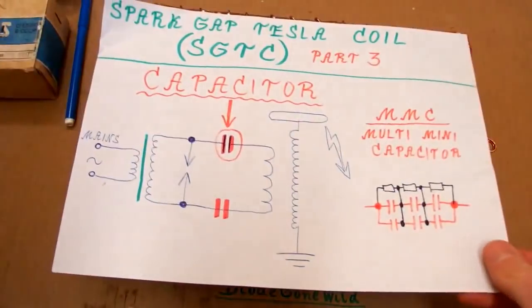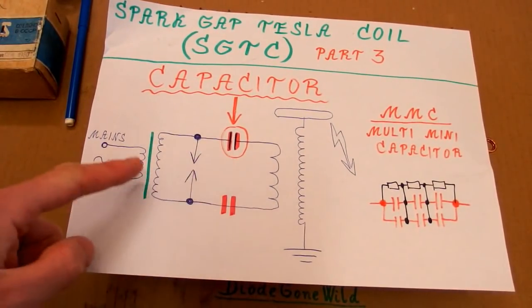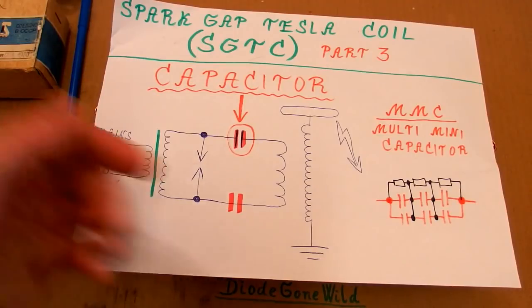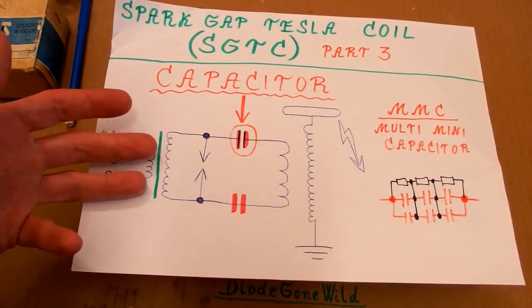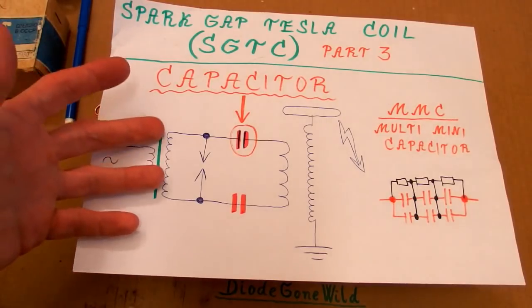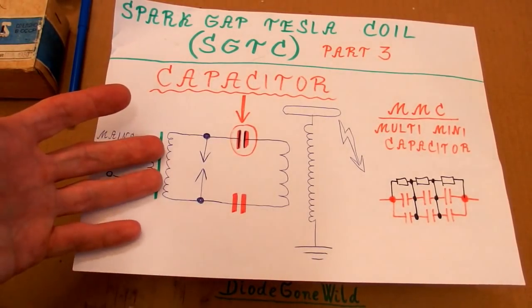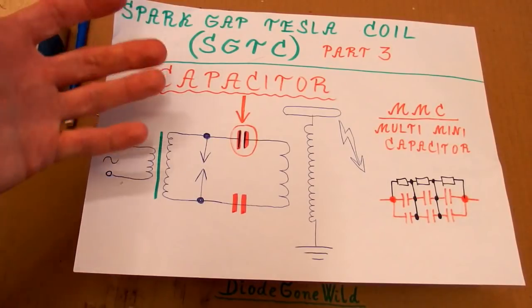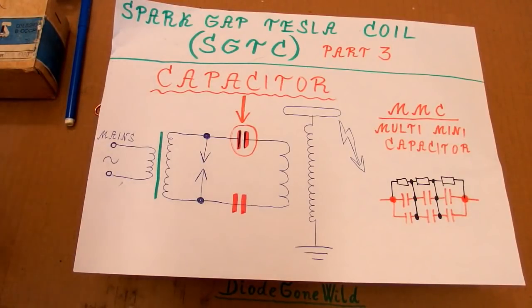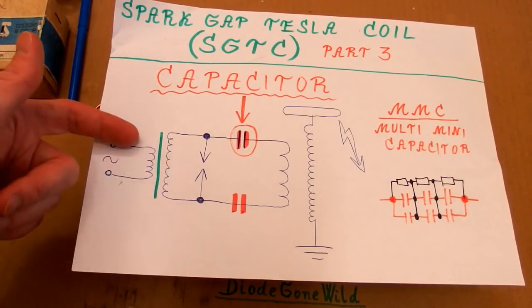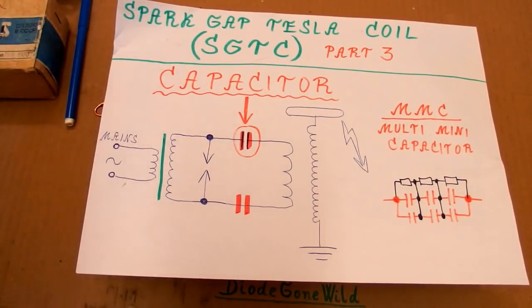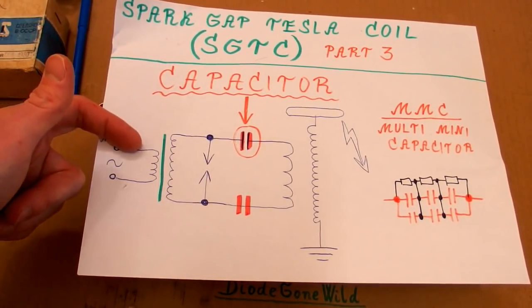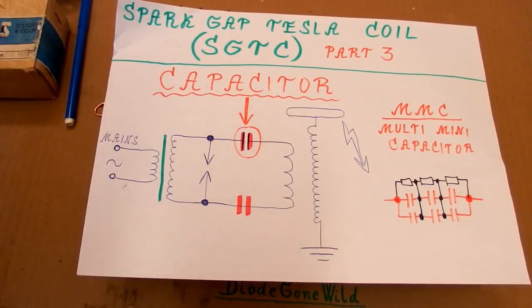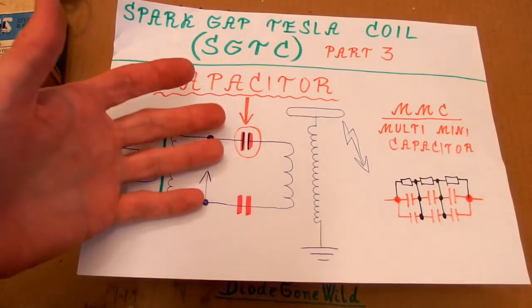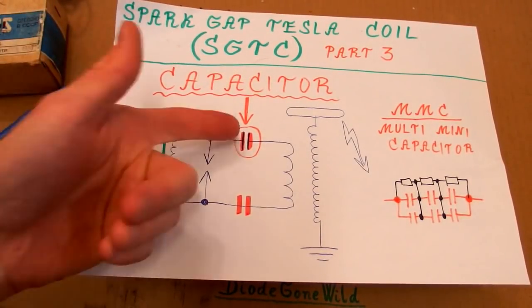And of course, one thing I forgot to mention earlier is that the capacitor shouldn't resonate with the transformer. The capacitor has some resonance frequency together with the inductance of the transformer, but this shouldn't be the mains frequency. Because of course the transformer has some inductance, either internal inductance because of the magnetic shunt in it or external inductance, some inductor to limit the current. And it doesn't matter if the inductor is on the primary side or secondary side. The inductance still transfers from the primary side into the secondary side and it can resonate. The resonance could basically boost the voltage to a point where it destroys the transformer or the capacitor.